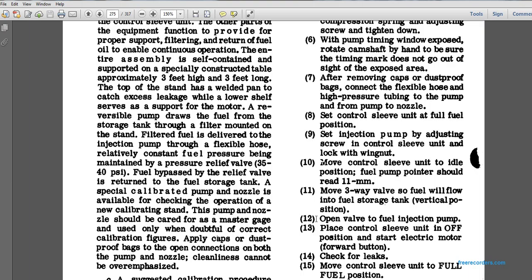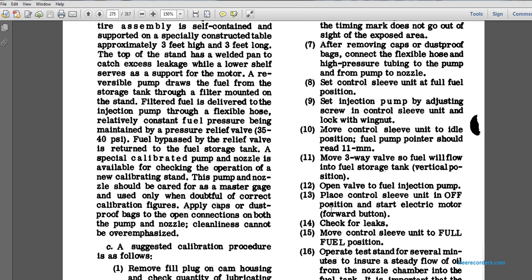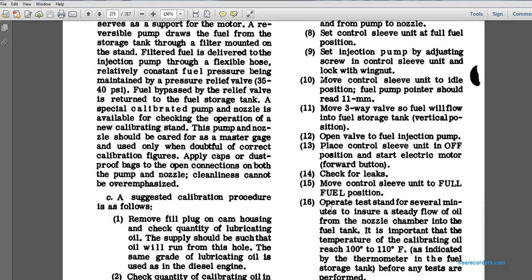Vertical position. 12. Open the valve to the fuel injection pump. 13. Place the control sleeve into the off position, starting the electric motor, forward button. 14. Check for leaks. 15. Move the control sleeve into the full fuel position.